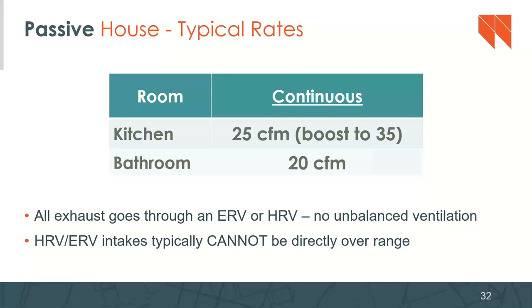Yeah, but good question. So in terms of passive house and what the rates are, these are like typical rates. Passive house is looking to do their ventilation through an ERV or an HRV. Unbalanced ventilation is not allowed. So in a kitchen, typically we're looking at 25 CFM continuous, and in the bathroom, 20 CFM continuous.